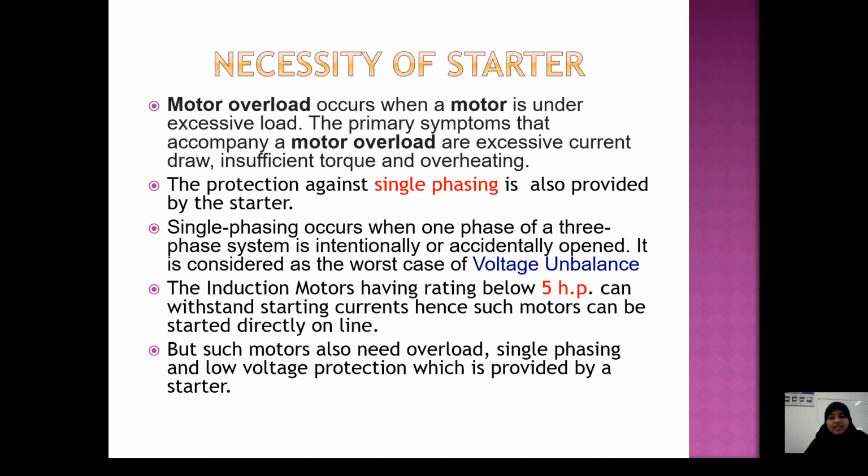Protection against single phasing is also provided by the starter. What is single phasing? In a three-phase system, RYB, three phases will be there. If one of the phases is accidentally or intentionally opened, it is considered single phasing. This is called voltage unbalance. The starter will protect the motor against single phasing also.